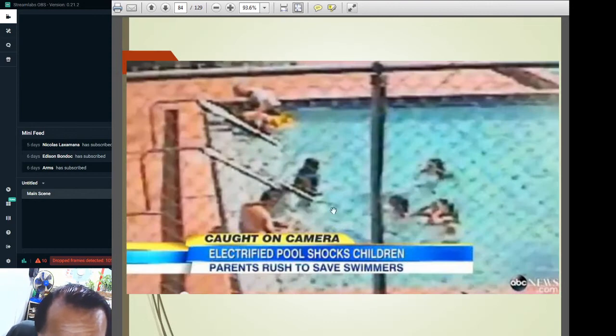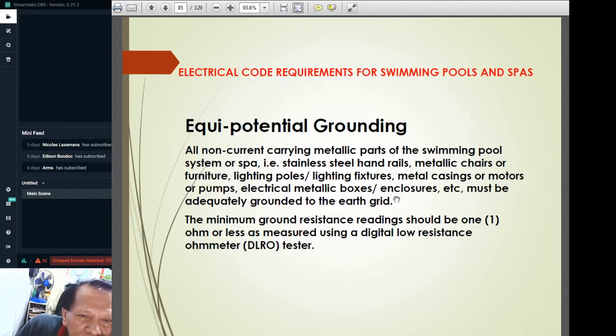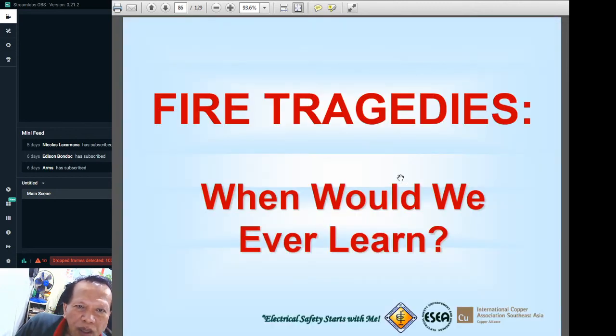And in the past there have been incidents, especially one, I remember, in Mandaluyong, in a hotel, I think, and also in Makati, in a residential building with a pool, where it is possible that the lighting circuits and some other wirings got wet, and there was no ground fault circuit interrupter provided, and therefore it posed danger to those people using the swimming pool. Equipotential grounding is very important to make sure that those who are using the swimming pool may not get an electric shock, no?